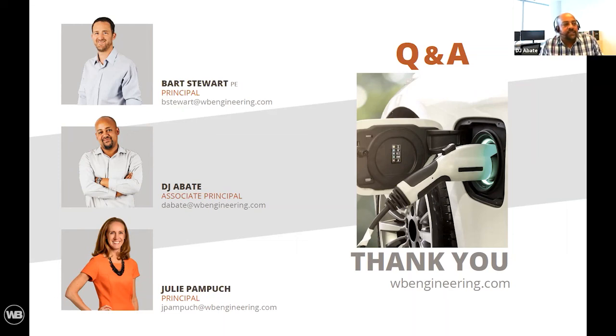No, because in older houses, some only have 100 amp electrical service. So if you have a 100 amp service and you're putting in a 40 amp load, that's something you might want to look at before you do anything. But most houses do have 200 amp service, so you should be able to absorb that 40 amps without any issue.